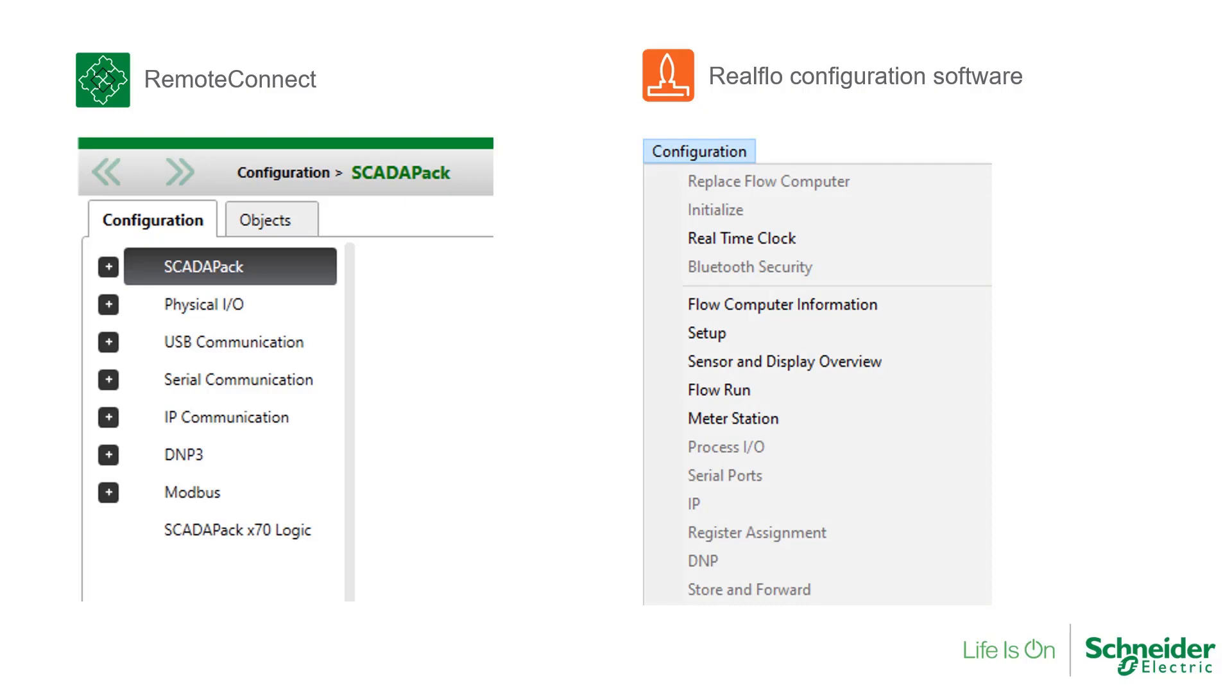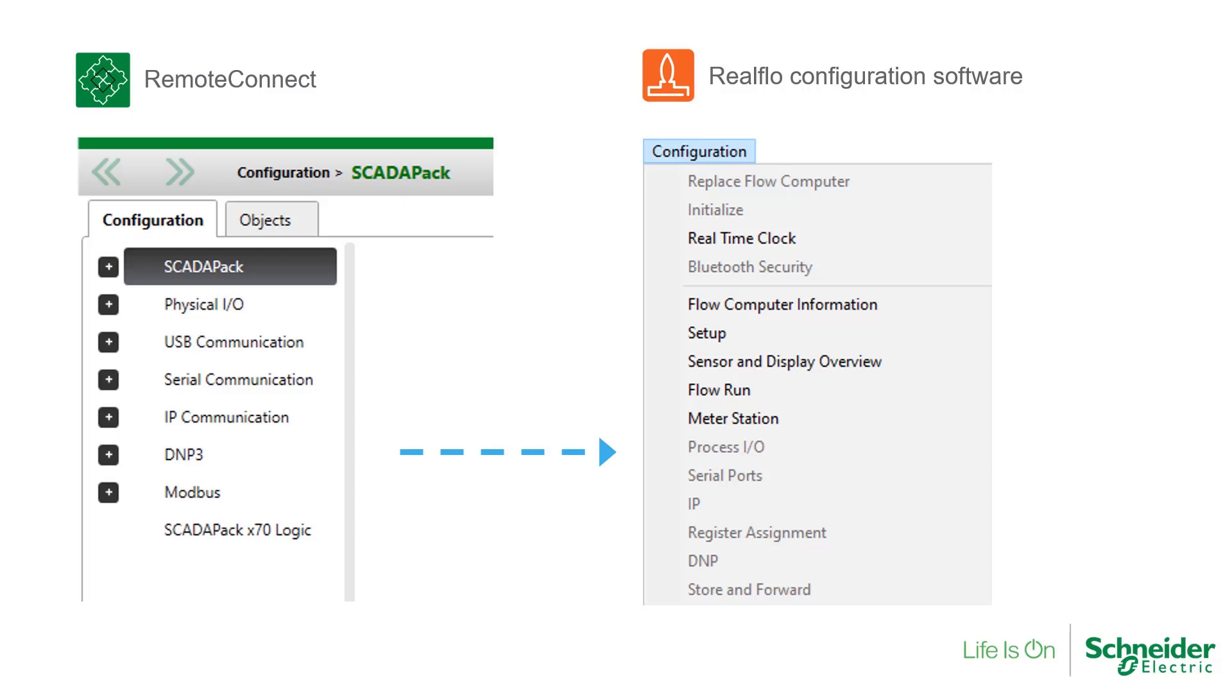This separation also avoids potentially writing conflicting data between two applications, RealFlo and the programming environment. Recall for SCADAPack 32 and SCADAPack 300 series, when Telepace or SCADAPack Workbench is used to configure the RTU, the software could overwrite the same communication port settings and protocol settings also written by RealFlo.